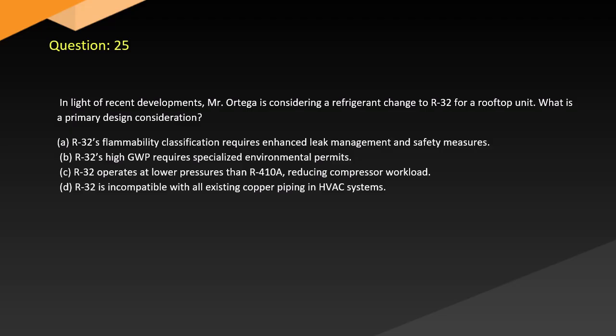Question 25. In light of recent developments, a technician is considering a refrigerant change to R32 for a rooftop unit. What is a primary design consideration? A. R32's flammability classification requires enhanced leak management and safety measures. B. R32's high GWP requires specialized environmental permits. C. R32 operates at lower pressures than R410A, reducing compressor workload. D. R32 is incompatible with all existing copper piping in HVAC systems.